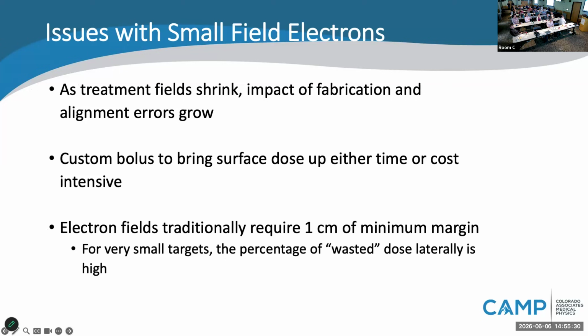So with that cone that we had forged, we were able to fix this one part of the problem at least, right? We had a 2 centimeter circle, and that's going to be 2 centimeters every single time that you use it. But we didn't really fix any of these bolus issues, and we didn't really fix any of these lateral margin issues as well. A 2 centimeter circle is going to be really pointed in that dose distribution, and you're going to have an effective treatment width of just a couple of millimeters.